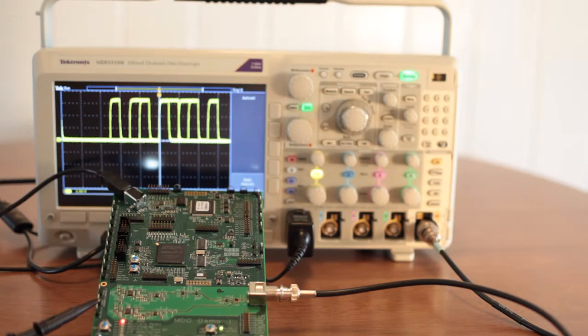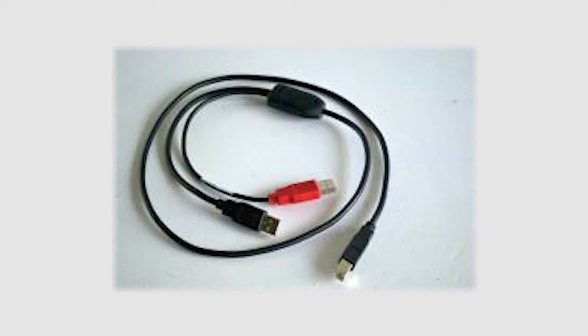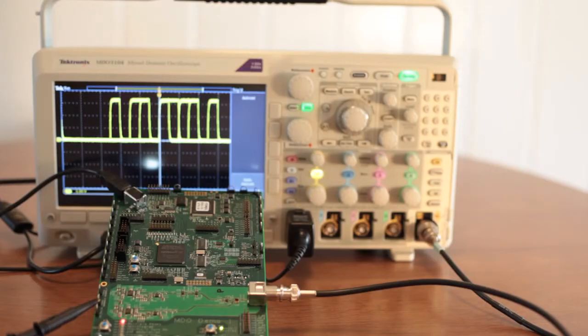Like much of today's electronic equipment, the demo board receives its power through a USB cable. In this case, it is an unusual T-shaped cable that has two A connectors at the input end. They plug into USB host ports on the oscilloscope. One of these USB connectors and associated cable would not have enough ampacity to power the 1.05 amp peak current that is required by the demo board. To avoid an overcurrent event, plug both A connectors into the oscilloscope USB ports before attaching the single USB B connector at the other end of the cable to the demo board.